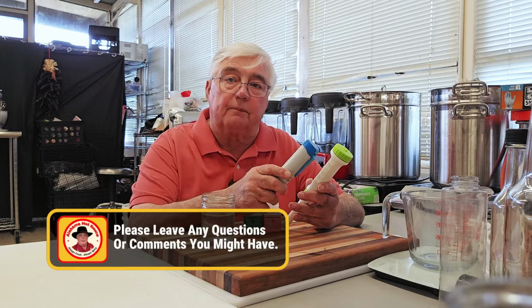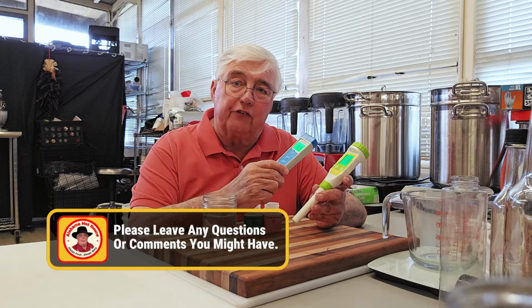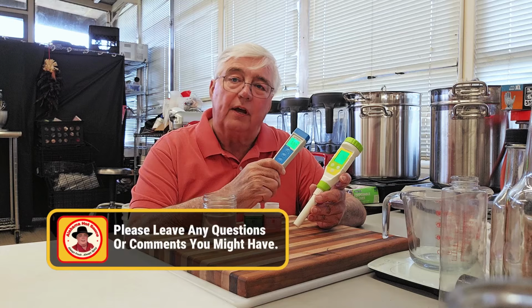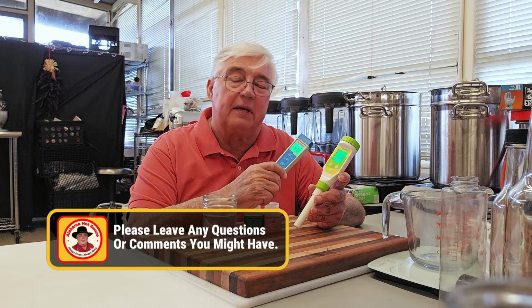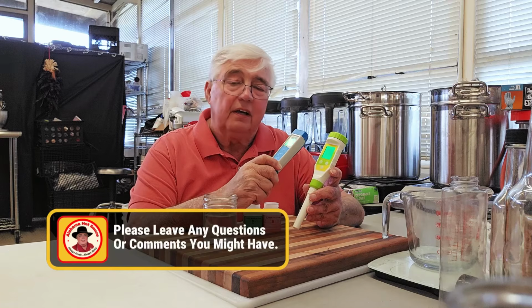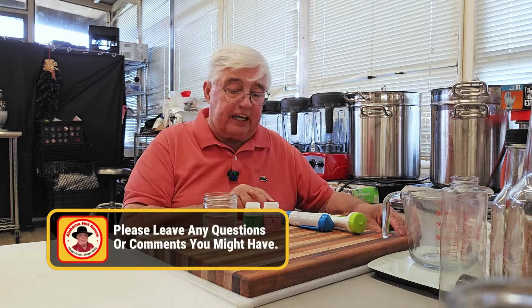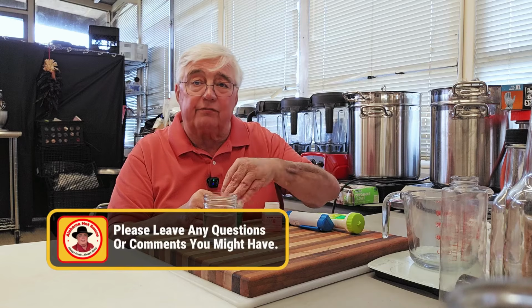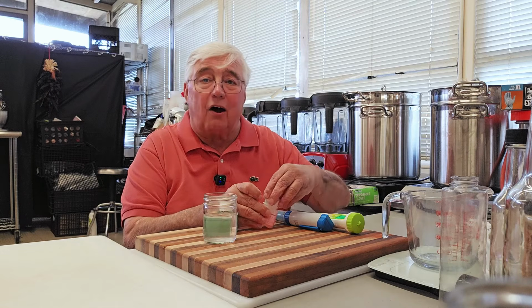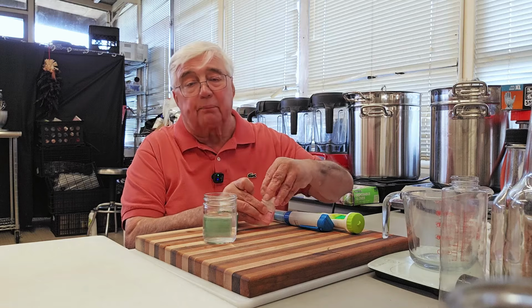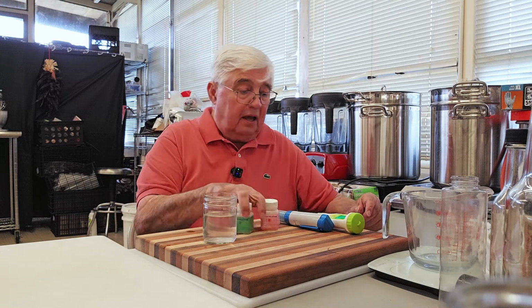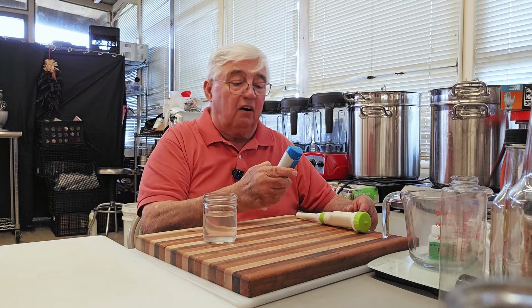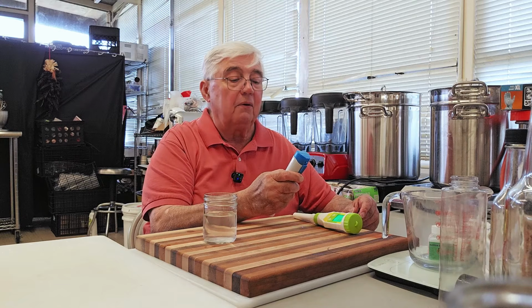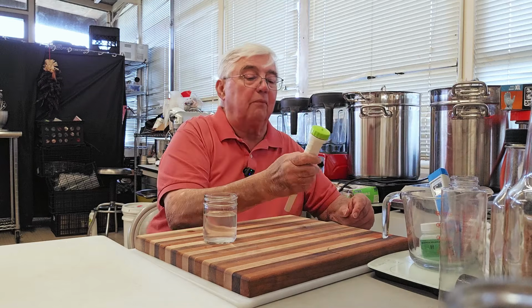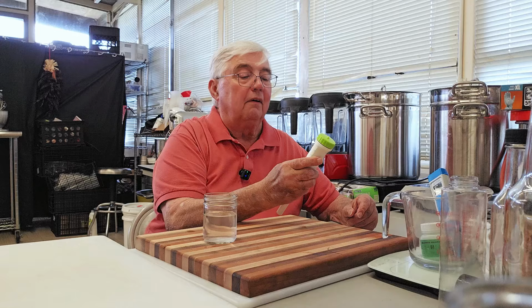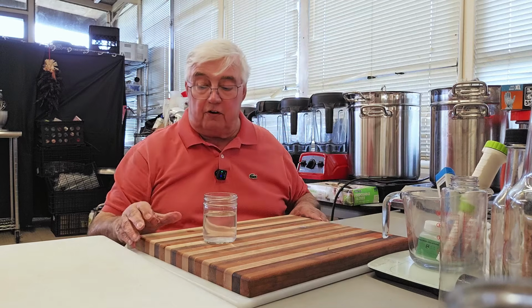Now, there's something else I want to point out to you. There's a sense out there that these meters are exceptionally sensitive. By that I mean not very mechanically robust. I don't believe that's the case. I don't keep my meters in any kind of case. I've dropped them. I've done all kinds of things. Now, if you drop it on the probe and break a probe, you've got to replace that. That happens on occasion. But I basically just keep my meters on my desktop, right here in this measuring cup. And they sit there all the time until I go to use them.